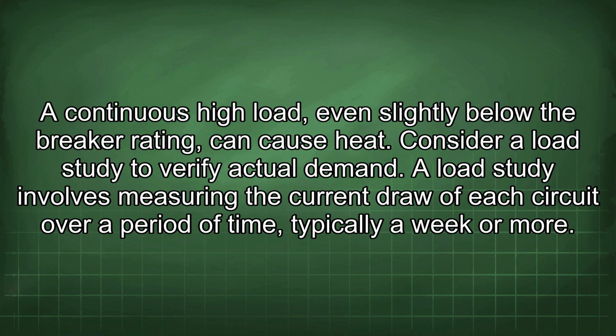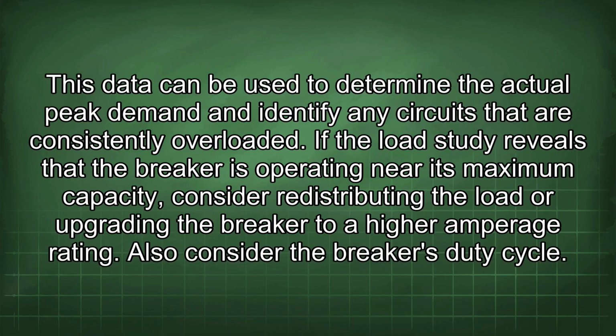A continuous high load, even slightly below the breaker rating, can cause heat. Consider a load study to verify actual demand. A load study involves measuring the current draw of each circuit over a period of time, typically a week or more. This data can be used to determine the actual peak demand and identify any circuits that are consistently overloaded.